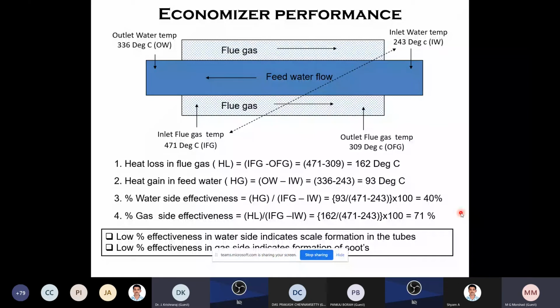And if the scale formation is there, you have to check the boiler water, whether the boiler water chemistry is proper or not. Because if the chemistry is not proper, there is a possibility of scale formation in the tubes. So that may affect the economizer performance. So how much heat is going inside? If the performance is very poor, the boiler efficiency will also decrease because heat is not being picked up here. So automatically it will be there. So the energy auditing team can take these remarks or observations and give their recommendations.